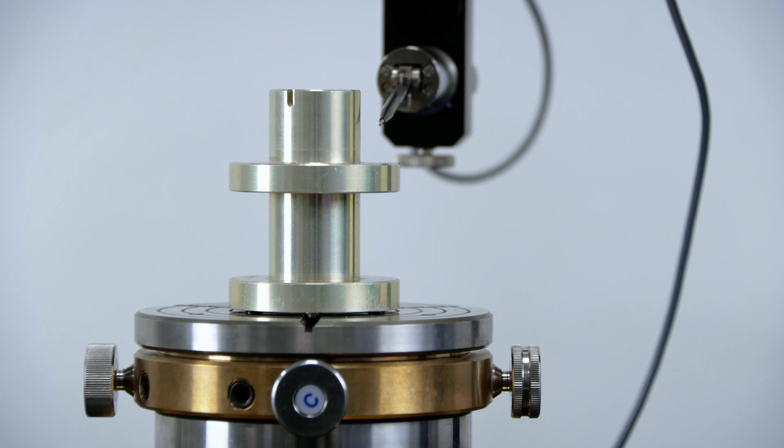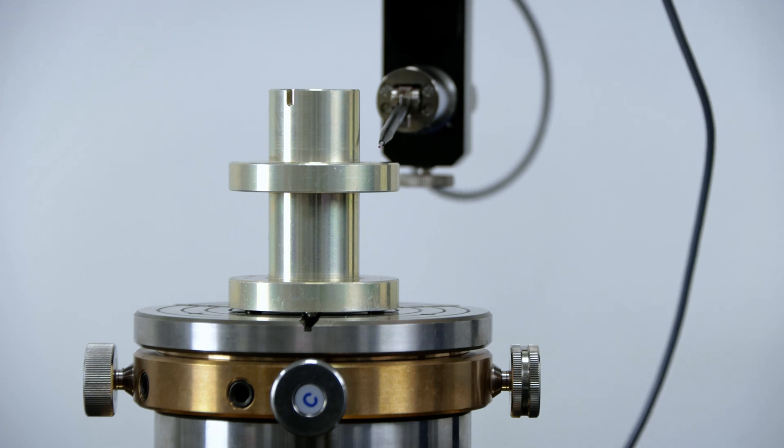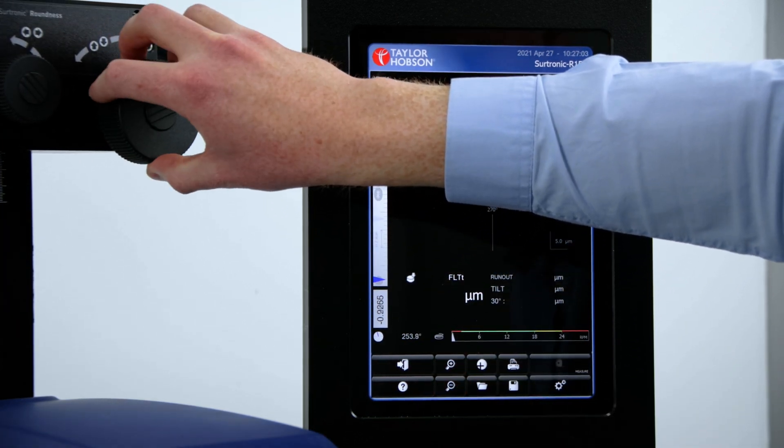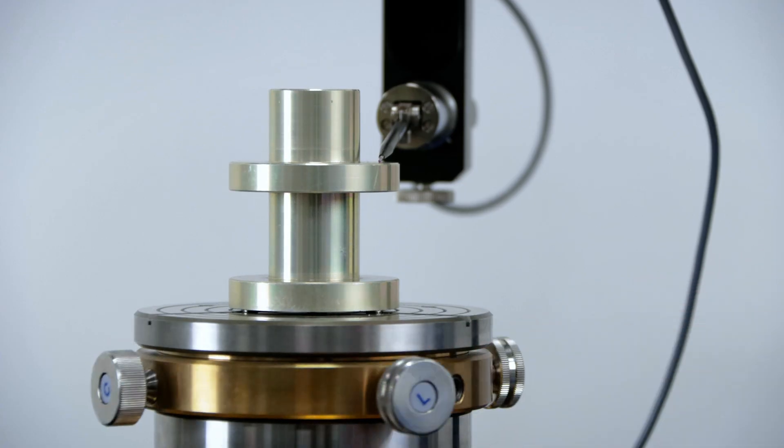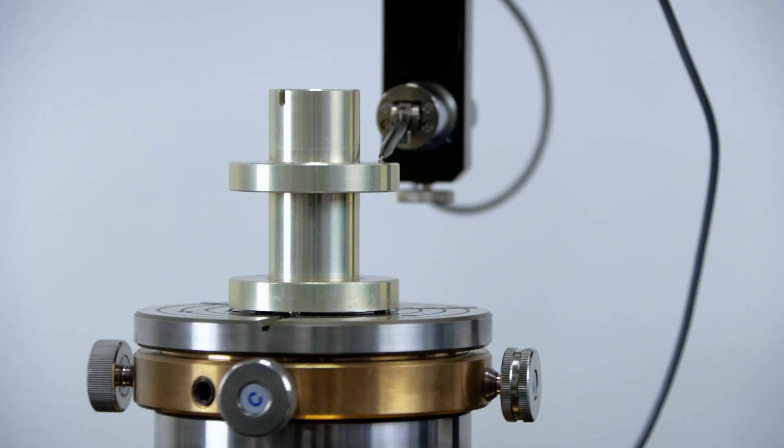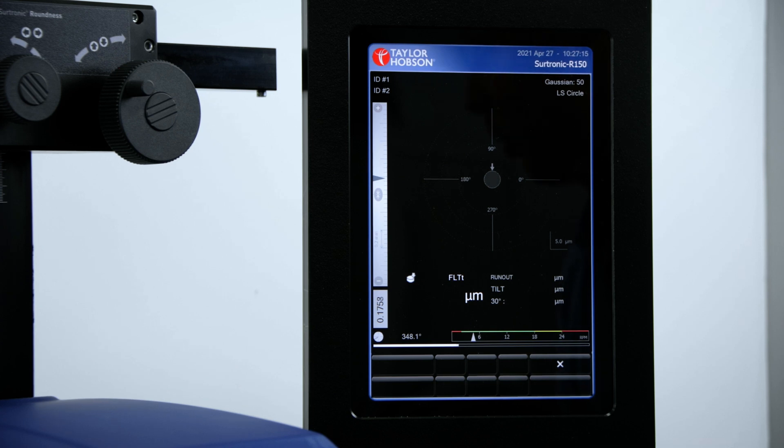To take a flatness measurement, we go into the flatness menu. I'm going to contact the gauge using the column. Once we're contacted, we can gently rotate the table and click measure. As before, the progress bar is moving forward.